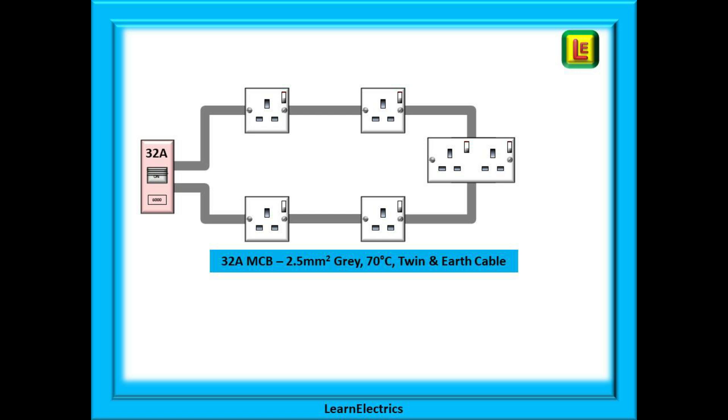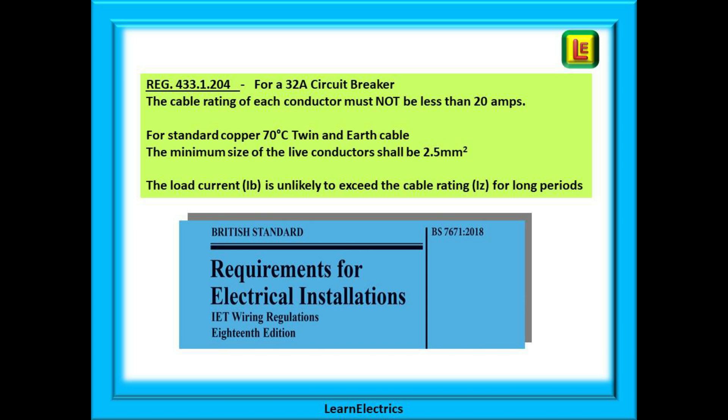We can begin with the wiring regulations. Regulation 433.1.204 tells us that for a 32 amp ring circuit the conductors, the line and neutral, must have a rating of at least 20 amps. It also tells us that for standard 70 degree twin and earth cable we should choose a size that is not less than 2.5 millimeters.